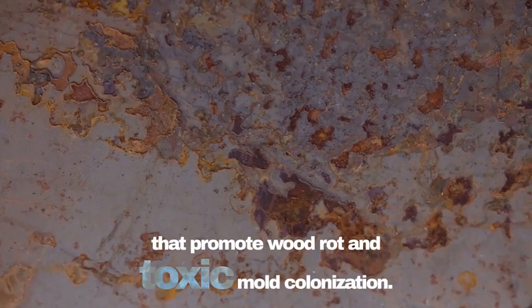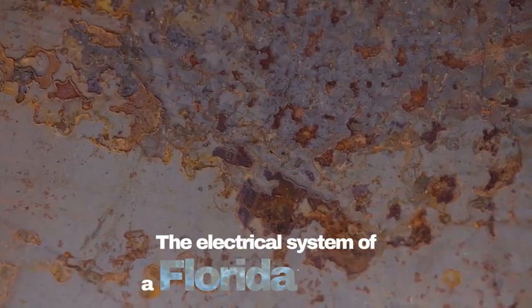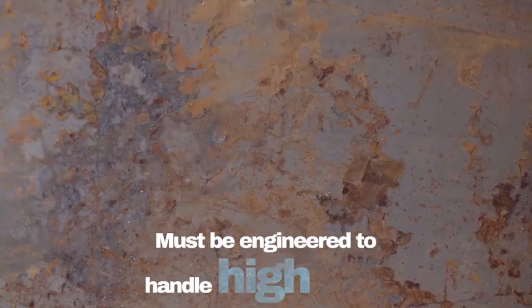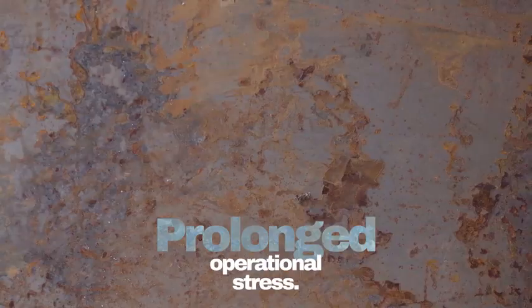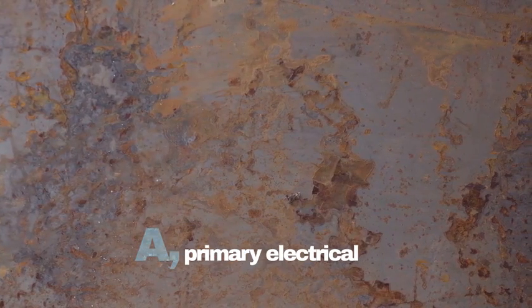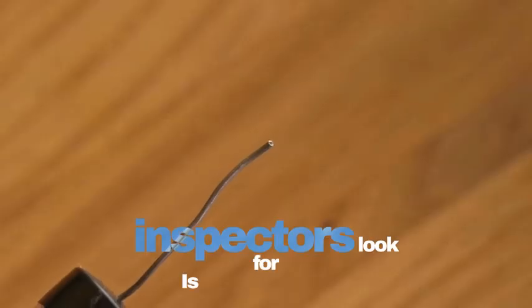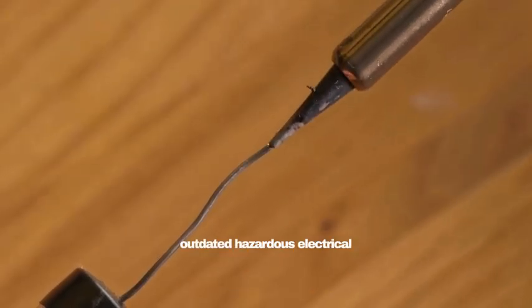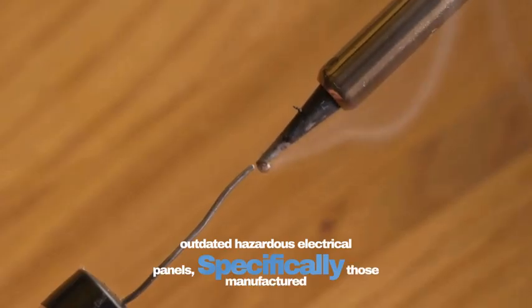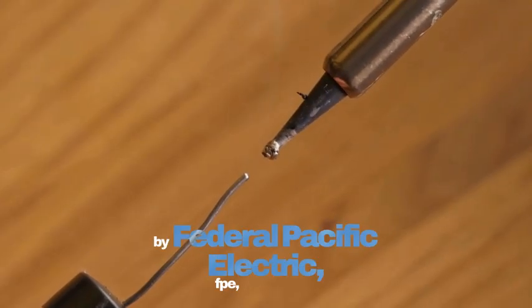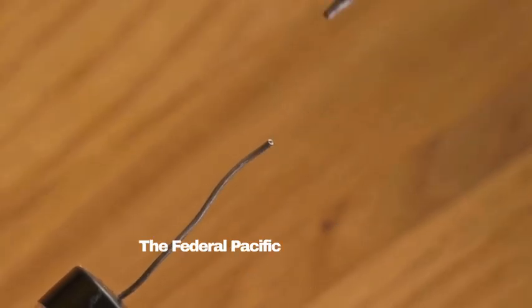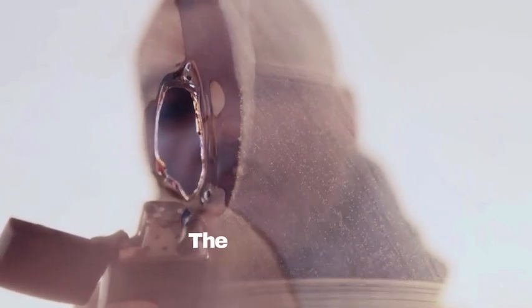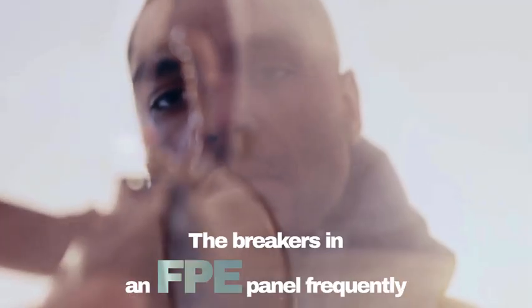The electrical system of a Florida residence must be engineered to handle high cooling loads while maintaining absolute safety under prolonged operational stress. A primary electrical red flag that home inspectors look for is the presence of outdated, hazardous electrical panels, specifically those manufactured by Federal Pacific Electric, FPE, and Zinsco. The Federal Pacific stab lock panel is highly dangerous due to a structural defect in its breaker design. The breakers in an FPE panel frequently fail to trip when they experience an electrical overload or a short circuit.